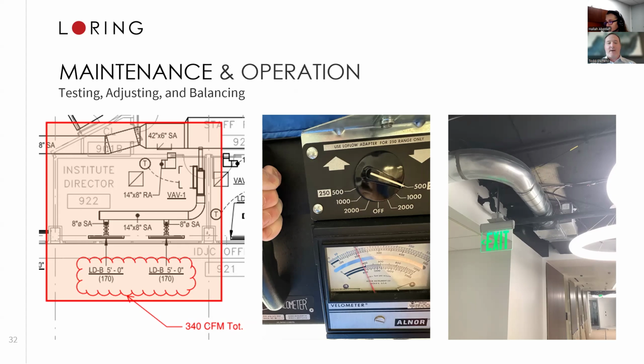So we were able to go out and measure the airflow at those linear diffusers, while at the same time looking at what the BAS was reporting. The set point for this system was 340 CFM. The BAS was saying that it was supplying 340 CFM, but when I put my duct airflow hood on top of it, we were only getting a little over 200 CFM actually delivered to those diffusers.